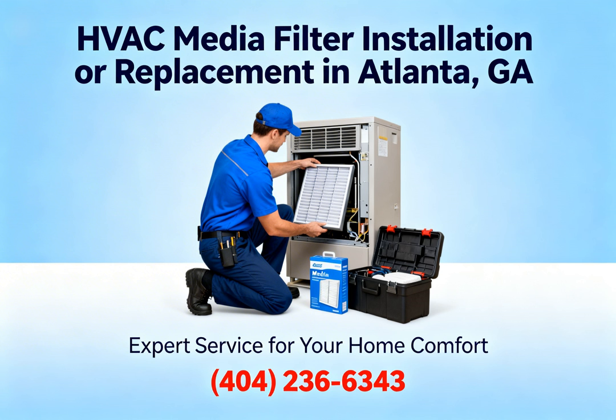Exactly. When dust and biological growth coat the evaporator coils, it acts as an insulator. The system has to run significantly longer cycles to achieve the same temperature drop. Because it's just working harder. Working much harder. That prolonged runtime degrades the compressor, wears out the capacitors, and grinds down the blower motor bearings. By stopping 98% of particulates before they ever reach the coils, the system maintains its day-one thermodynamic efficiency for years.